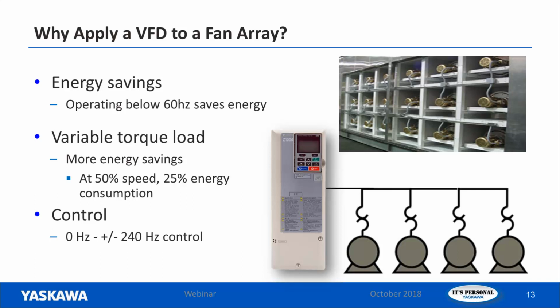Next would be, with fan arrays, we're talking about a variable torque load. So when you have a motor driving a fan that's moving air, that is a variable torque load. Yes, at full speed, 60 hertz, you're going to be pushing the maximum amount of power, and you're going to be getting the most resistance on the fan blades. But it's not linear. At 50% speed, you'll be at only 25% roughly energy. So you can get some pretty good savings as you go down the scale from 60 hertz.